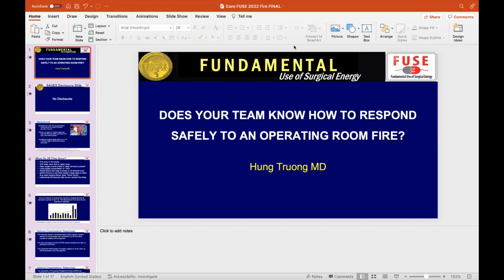Second one is you've got to route your current vector in the right way. So if you do an inguinal hernia, but you put the dispersive electrode up on the shoulder so that the current passes from the inguinal hernia up through the cardiac implanted device through the shoulder, that doesn't do any good. You want to put the dispersive electrode so the current goes through the body away from the cardiac implanted device.